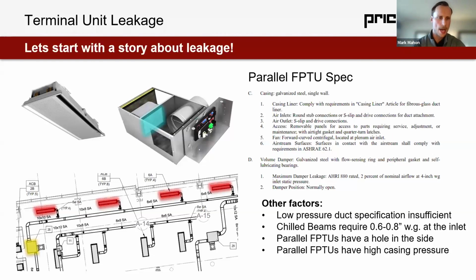So when we look at the schematic on the left, we have 4 chilled beams being served by 1 fan powered box. And that means the pressure of that ductwork is realistically over an inch, so a lot higher than the 1/4 inch we'd maybe normally see in low pressure ductwork. Another factor here is the fan powered box that they chose. I would argue a misapplication, or not the right product to use here.